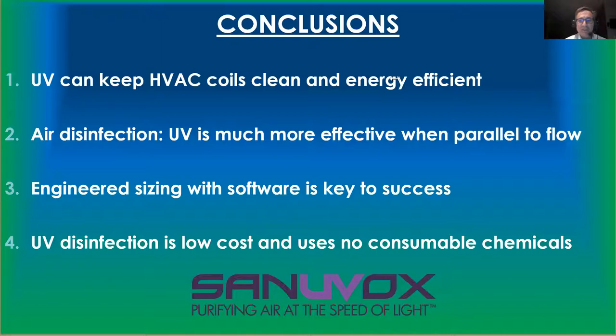It can be done, but it's very tricky because all of a sudden you can have some mold, some spores up in the air, and sometimes you have not. It's very erratic as measurements, very difficult to get a good grasp on airborne bacteria. And some of them are difficult to cultivate also. On the coil, they pretty much grow by themselves. It's pretty easy to get samples. In the air, it's much more difficult. We've done that before with air sampling. You need a statistical way of doing it. You need to take lots of samples at different times of the day and do a proper comparison.